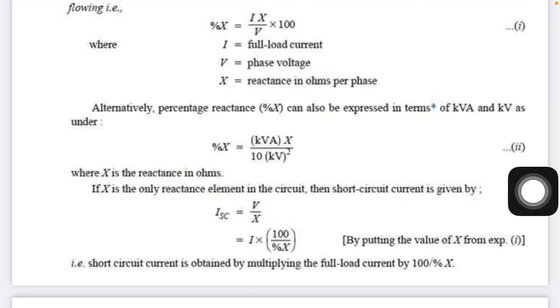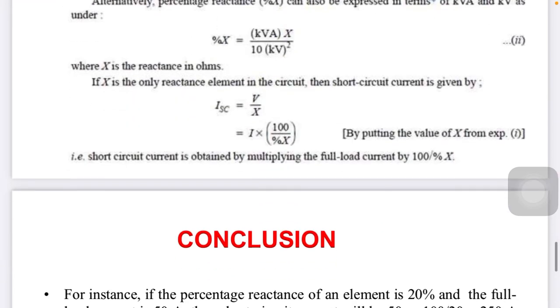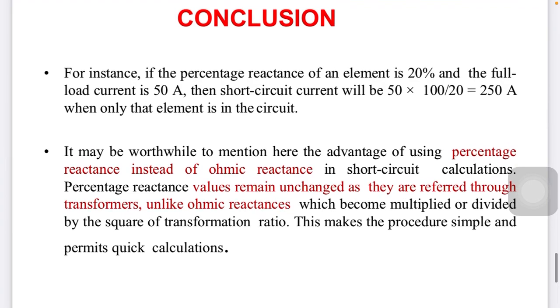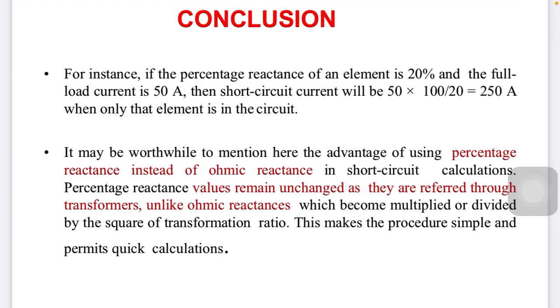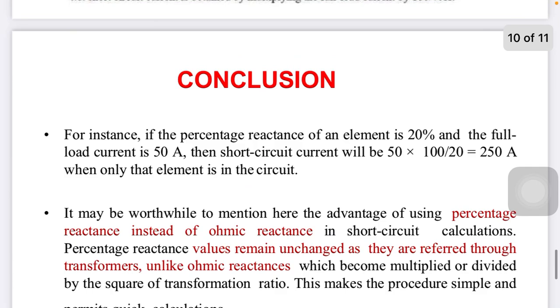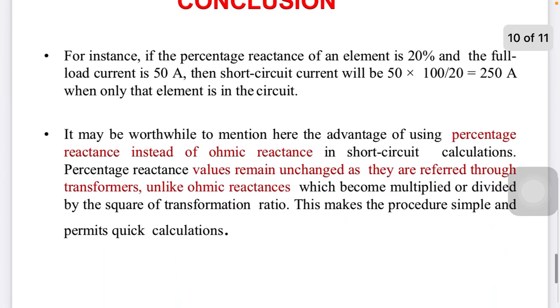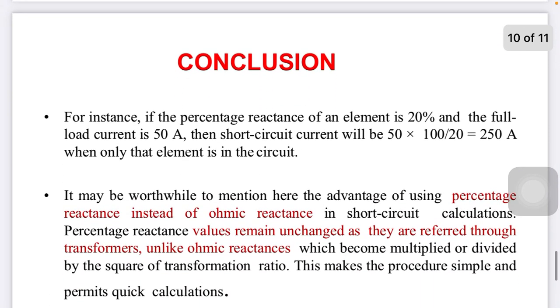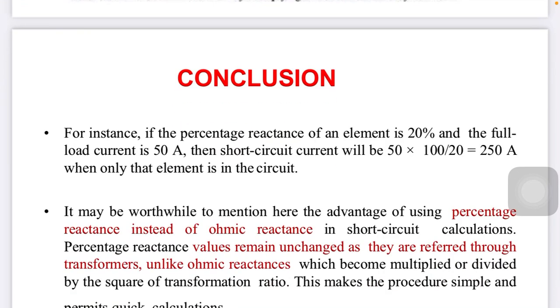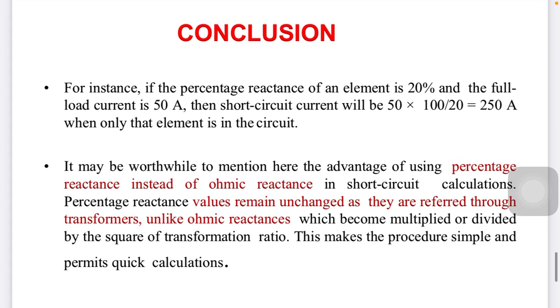So the short circuit current is obtained by multiplying the full load current by 100% divided by %X. For example, if the percentage reactance of the element is 20% and the full load current is 50 amperes, then the short circuit current is 50 × (100/20) = 250 amperes. From the next lecture, detailed examples of short circuit and different types of faults will be discussed.